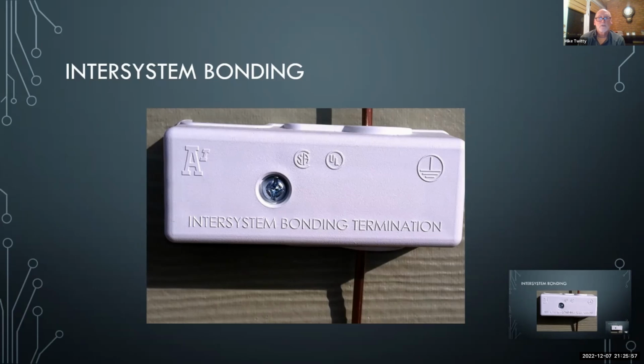So they required this, and this is where they can put their equipment. And this is the grounding electrode conductor that goes through this. It's not broken in here. It goes through. It can't be spliced, and it ties through there, and then their stuff gets bonded to the grounding electrode system by this termination.